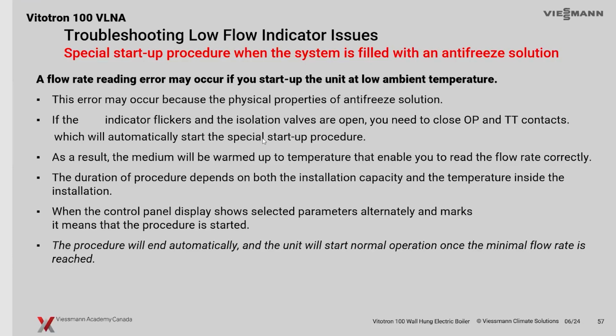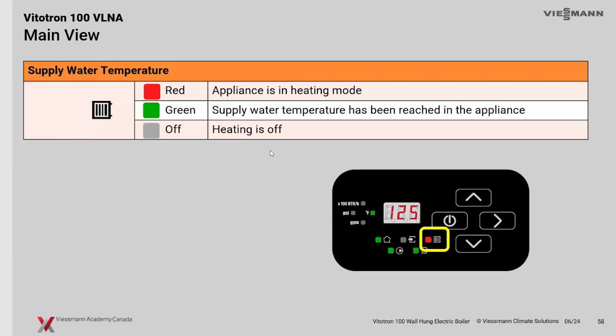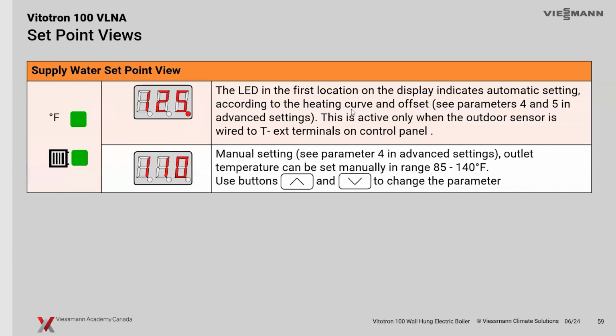It has to warm up a little bit. You might get that flashing little pump output, just to let you know that if that thing is flashing, you might be dealing with a slightly slower flow rate, and it's going to build up if we're heating up that glycol in that time. As I mentioned, space heating, red, we're heating up, the boiler's heating up right now. If it's green, we're essentially supplying the temperature water that we're looking for, the set point.